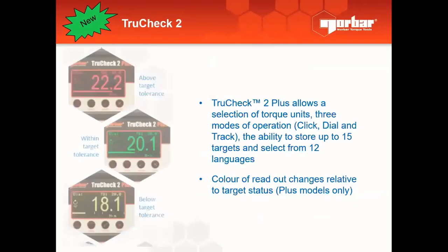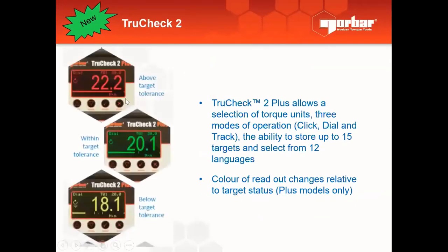So you can clearly see where it's red, it's over your target tolerance. When it's green, it's within your tolerance. Amber is below your target. It's able to select different types of torque units and different modes for operation, like click type, dial type, or track mode, and you're able to save up to 15 targets. The previous model wasn't able to save any targets.